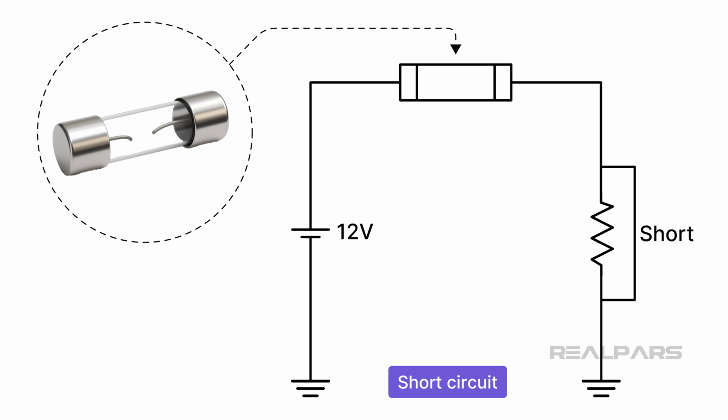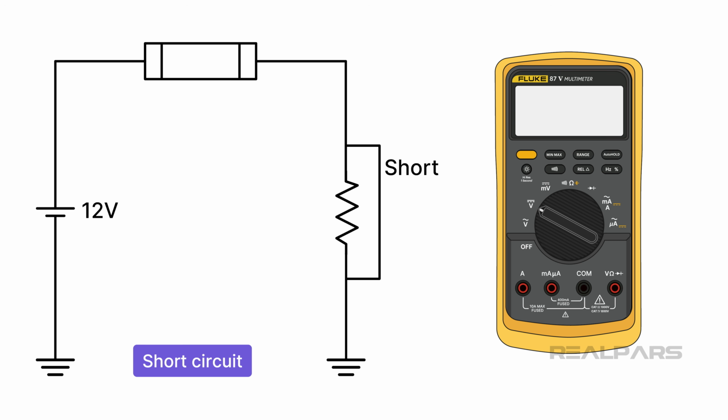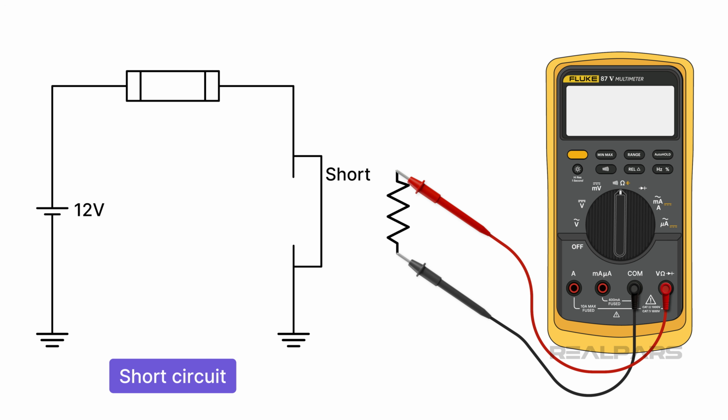Short circuits usually result in an open fuse or a tripped protective device, often eliminating the use of live circuit voltmeter tests. They are best confirmed by resistance testing, which requires following safety practices for ohm meter use and, where required, lockout-tagout procedures.